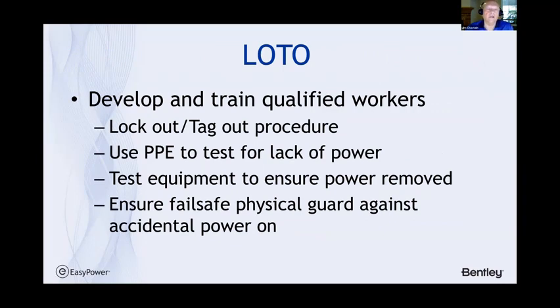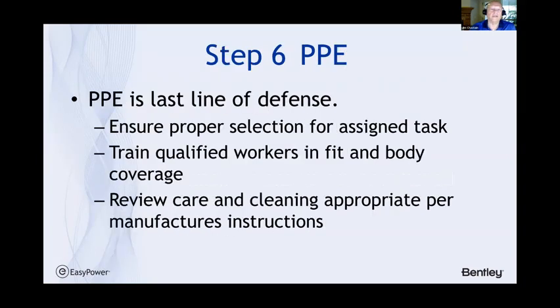Lockout tagout is required to ensure the equipment's been de-energized, and this is required training for anybody in electrical energy employment to be re-upped every 3 years or sooner if the equipment is changed. Then step 6 is to consider PPE as the last line of defense. You want to ensure the proper selection and assigned risk of the task involved. Train qualified workers to be able to properly wear and make sure their body parts are covered as required. And then it's important for the provider or the user to review the care and cleaning appropriate to the manufacturer's instructions.